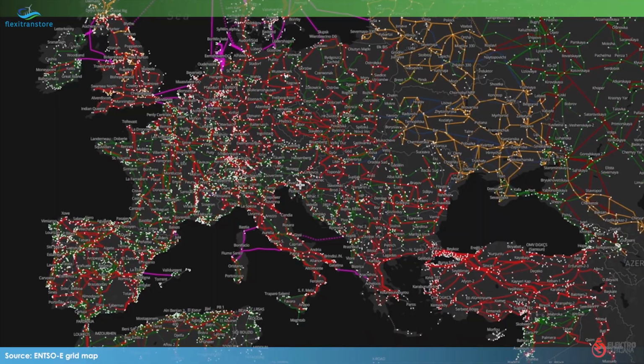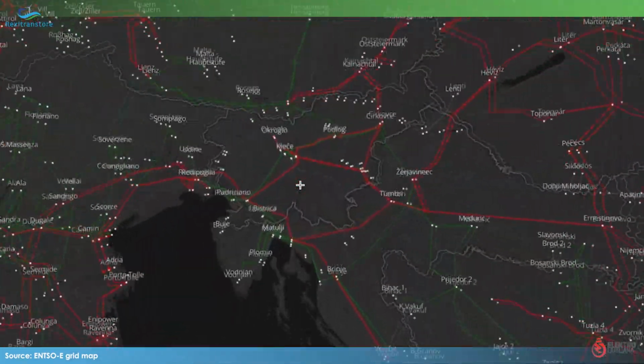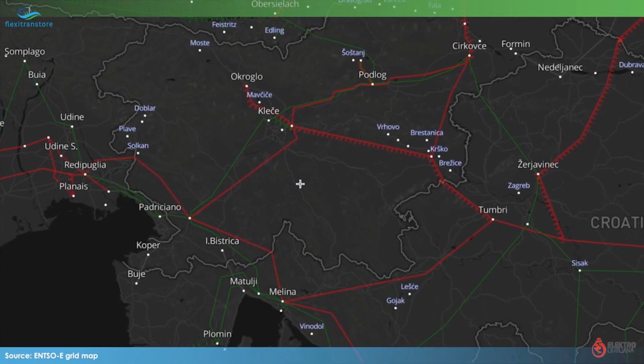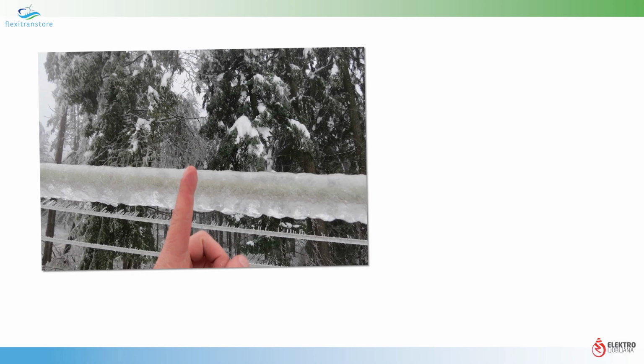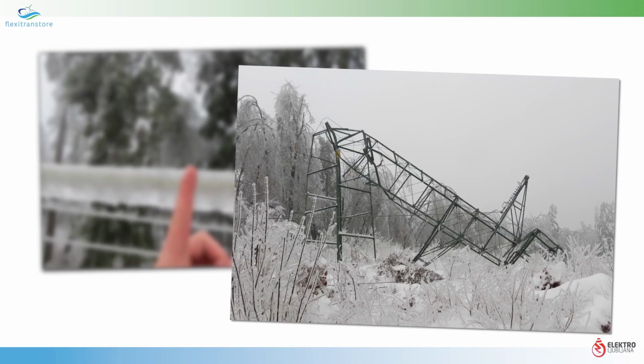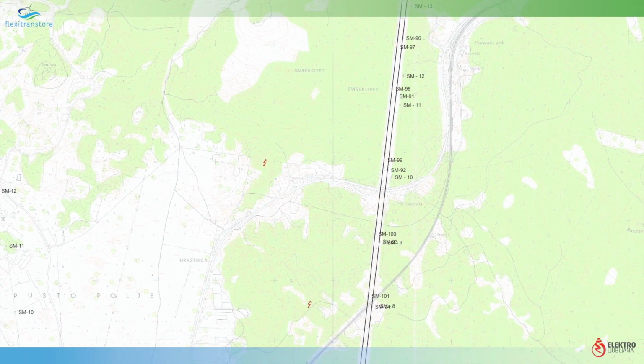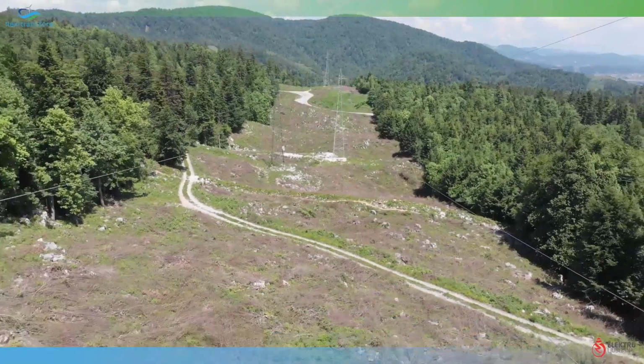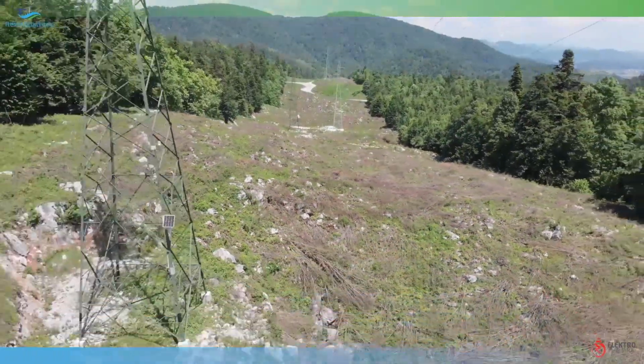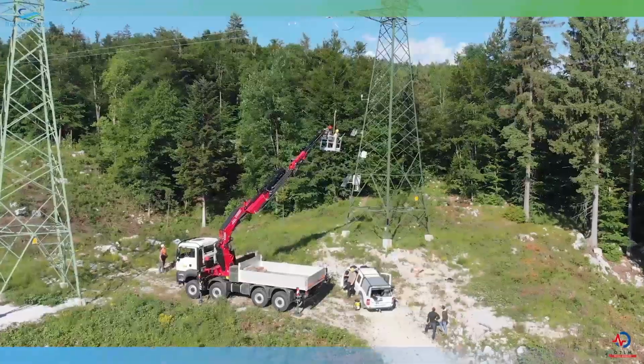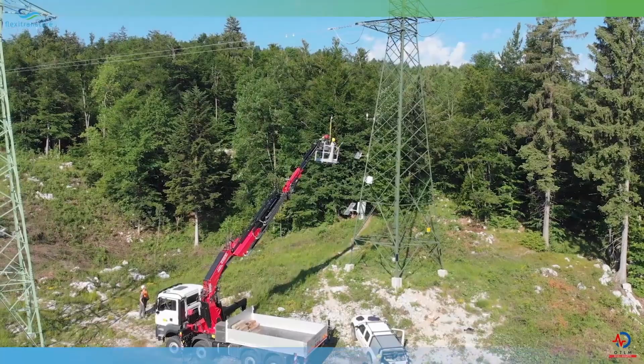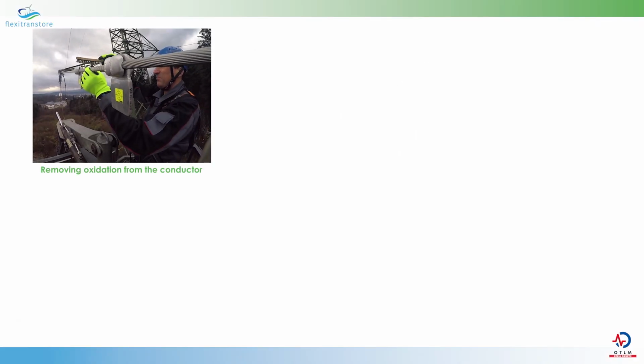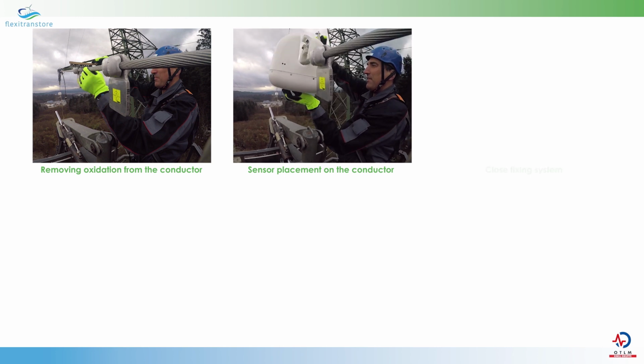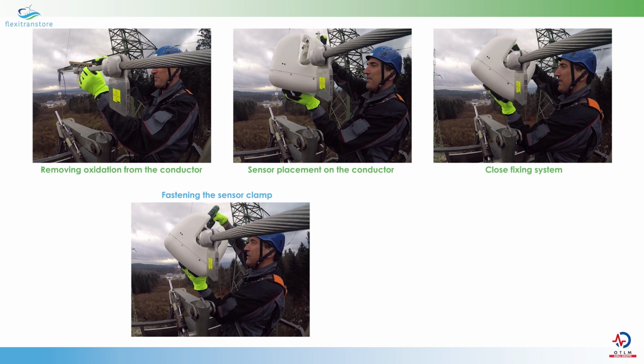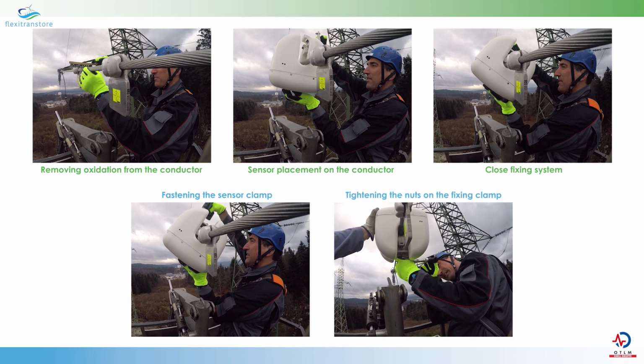The focus of the project is on the Klecce-Logatec 110 kV line, which plays an important role in the Slovenian electricity system. It is responsible for energy transfer between Ljubljana and the middle of the country. There was an icing event in 2014 which caused several towers of this power line to collapse. Redispatching actions and ampacity control are possible on this line, which facilitate the prevention of icing events. The Klecce-Logatec line seemed to be a good choice for demonstration activities. In this part of the video, I will show you the installation of the OTLM sensors. Removing oxidation from the conductor, sensor placement on the conductor, close fixing system, fastening the sensor clamp, finally tightening the nuts on the fixing clamp.